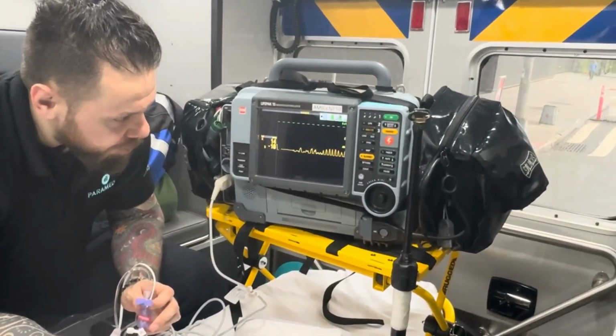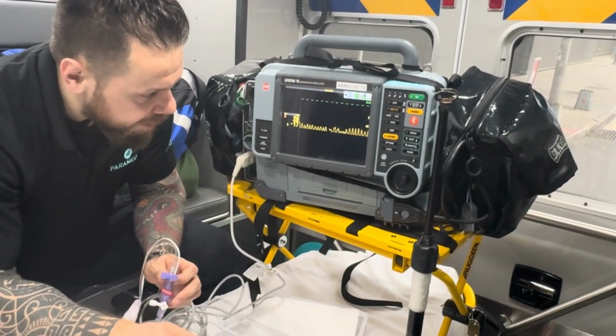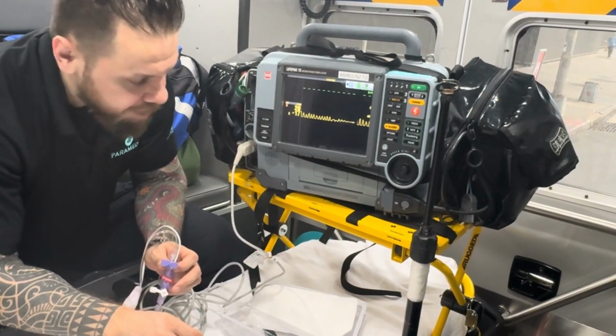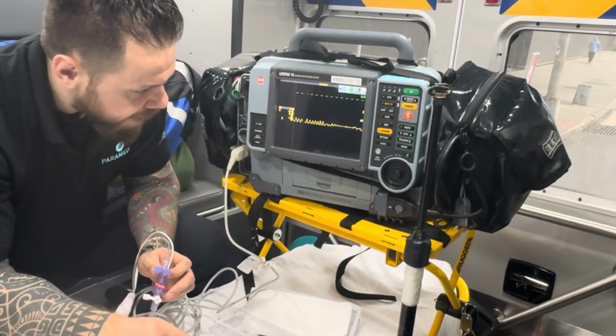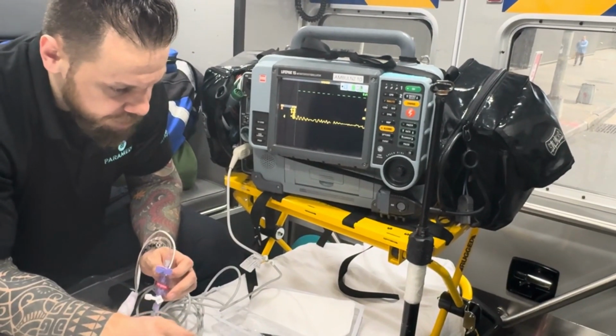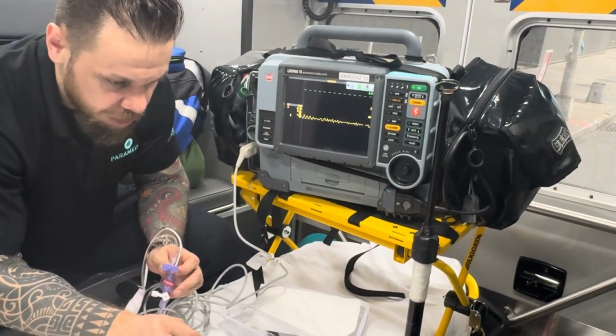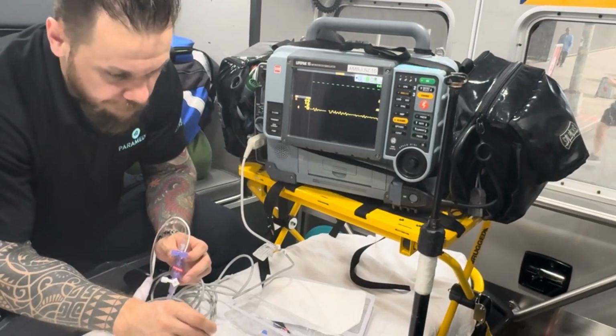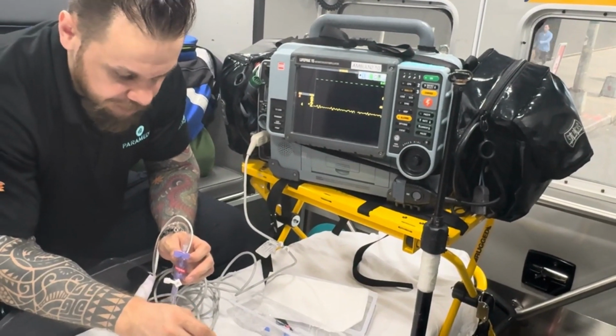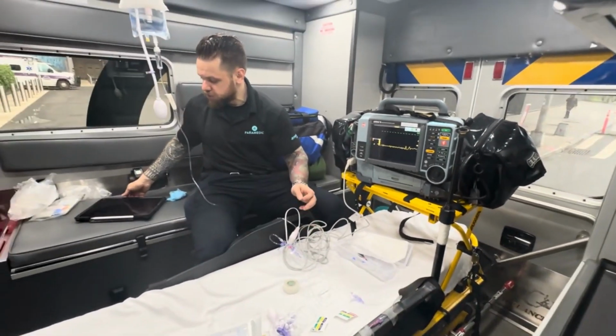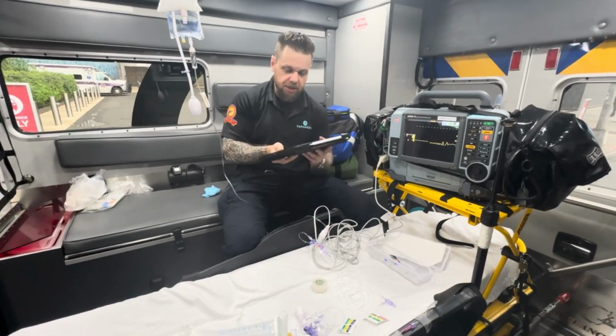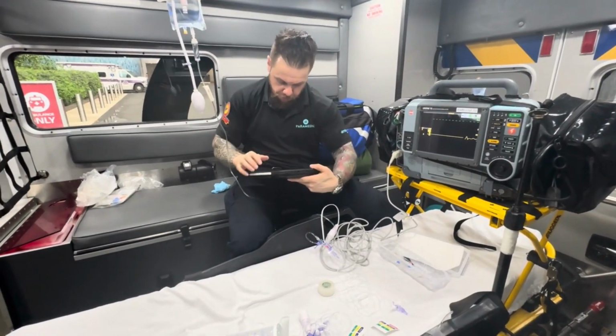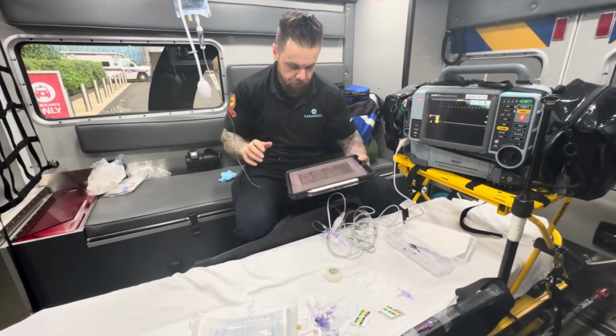Now, are you done yet? No, you're not done yet. You have zeroed your line and put the transducer on the appropriate side, but we have to perform what's known as a square flush test to know if the system is properly damped or overdamped, and if it needs any correction. So let me show you again the diagram so you guys can see what I'm talking about. We're going to perform a fast flush test, and I'll show you the waveforms.